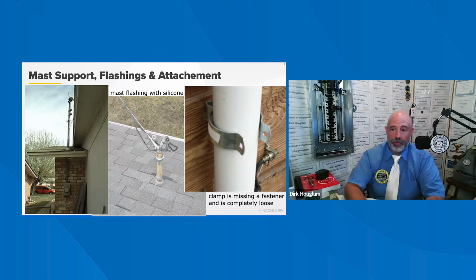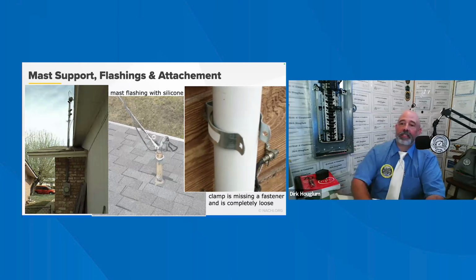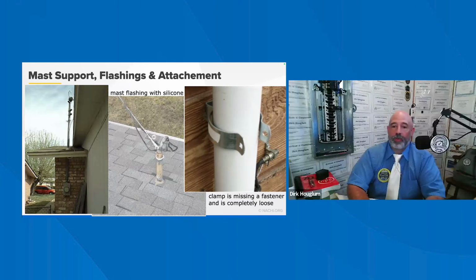As with other projections through the roof surface, the service mast should be adequately flashed to prevent the water from getting into the building. It is not unusual to see signs of water leakage through the roof due to poor mast flashing. Because the mast is generally outside of the conditioned space, these leaks commonly go unnoticed for years, causing considerable damage to the roof sheathing and fascia.